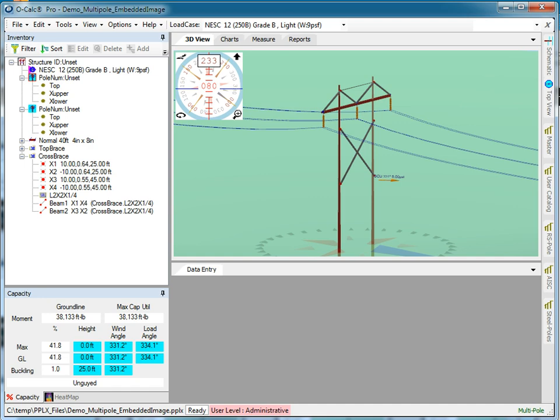O-Calc makes a node and beam classic finite element analysis structure and performs analysis on it for each of the 360-degree wind sweep angles and for all of the various loads, applying all the various load rules.